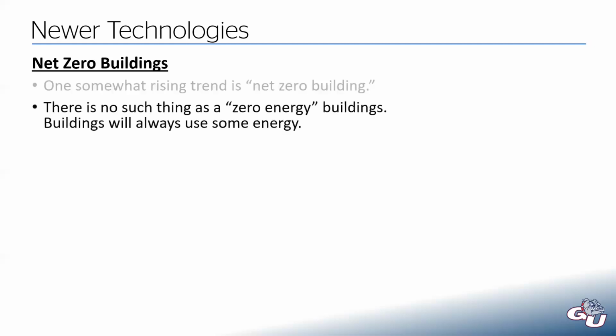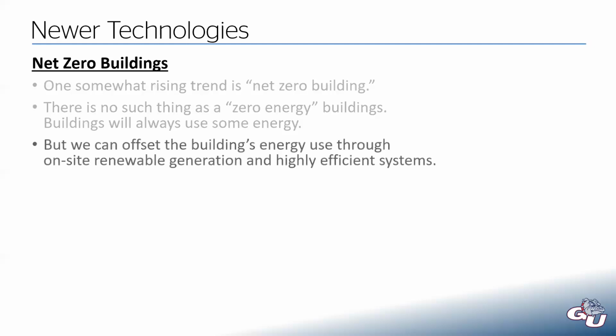So there is no such thing as a zero energy building. Net zero and zero energy are not the same thing. Buildings will always need to use some kind of energy. To run a pump or a fan or to do anything, we have to use energy. So zero energy, that's not the right term. But what we can do is offset our building's use through either on-site renewable generation and highly efficient HVAC systems. And I said either one of those, but really it has to be both. We have to have some sort of on-site renewables in addition to extremely efficient systems.